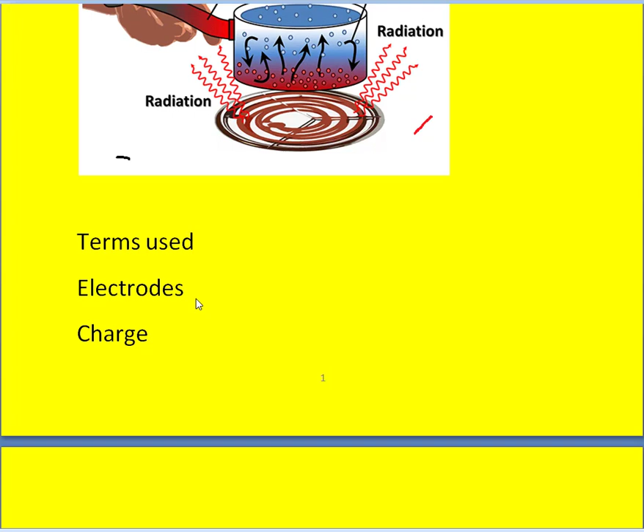Next, coming to the terms used in the heating methods: electrodes, charge, power transformer, etc. So what is meant by electrodes? These are the essential elements in all the furnaces. Charge is nothing but the material which is to be heated. The power transformer is used in the arc furnace to get low voltage with high current at the secondary side. Normally their rating will be minimum 50 kVA to 12 MVA.